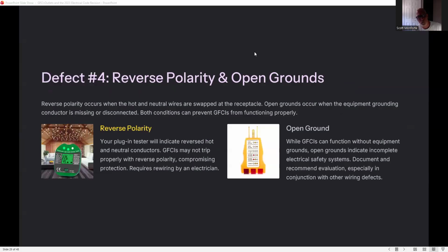Defect 4, reverse polarity and open grounds. Reverse polarity occurs when hot and neutral wires are swapped at the receptacle. Open grounds occur when the equipment grounding conductor is missing or disconnected. Both conditions can prevent a GFCI from functioning properly. Reverse polarity: your plug-in tester will indicate reverse hot and neutral conductors. GFCIs may not trip properly with reverse polarity, compromising protection, requiring rewiring by an electrician. Open ground: while GFCIs can function without equipment grounds, open grounds indicate incomplete electrical safety systems. Document and recommend evaluation, especially in conjunction with other wiring defects.